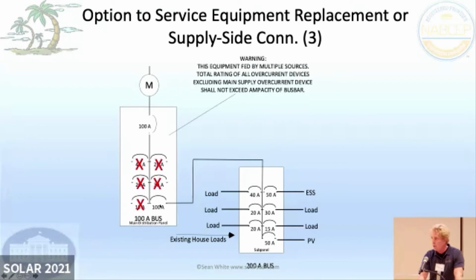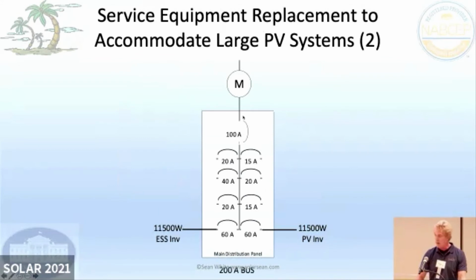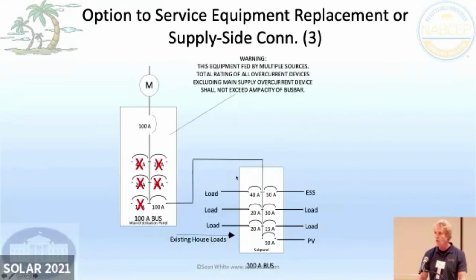And so that's what I called the sum rule. So just like, you can't add any more breakers. You've got to put a label there. It says the sum of all the breakers does not exceed the rating of the bus bar. And then you go over here and you put a 200 amp bus. Heck, why not a 400 amp bus? Put a big old bus bar and it's fed by a 100 amp breaker. And so then you have all the benefits of this right here. So some people are calling that the Hawaiian tie-in.